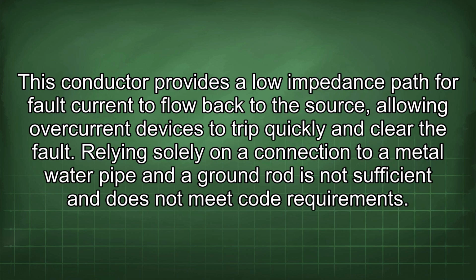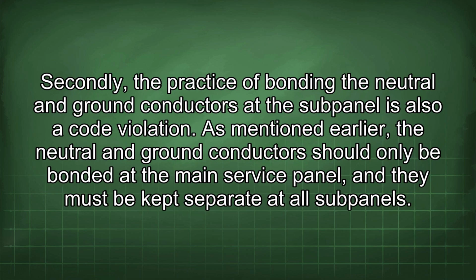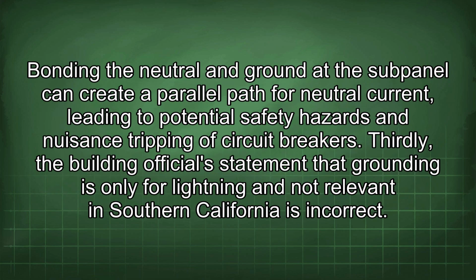Relying solely on a connection to a metal water pipe and a ground rod is not sufficient and does not meet code requirements. Secondly, the practice of bonding the neutral and ground conductors at the subpanel is also a code violation. As mentioned earlier, the neutral and ground conductors should only be bonded at the main service panel, and they must be kept separate at all subpanels. Bonding the neutral and ground at the subpanel can create a parallel path for neutral current, leading to potential safety hazards and nuisance tripping of circuit breakers.